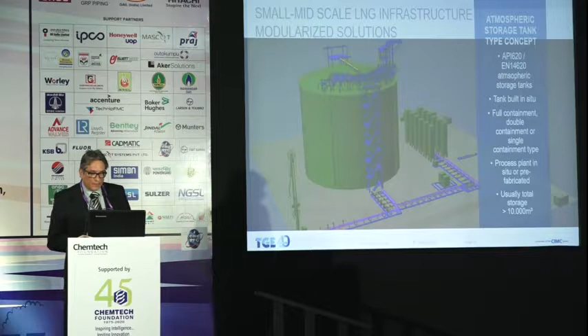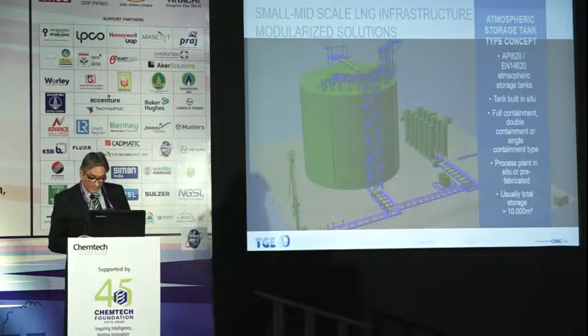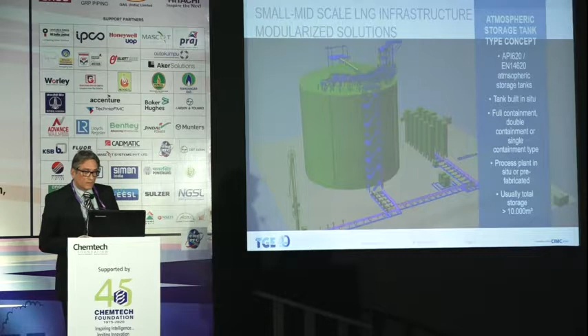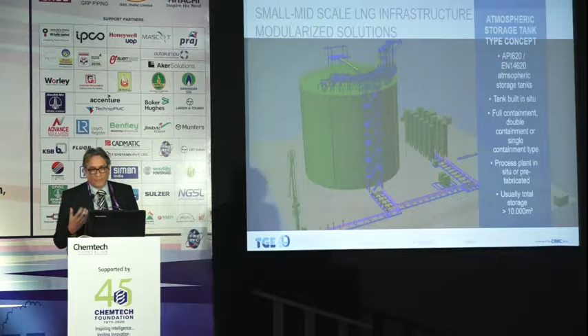authorities like to see a full containment solution, which is absolutely state of the art. Also here, as you can see, this is a very standardized and modularized design approach. This type of storage is usually applied for storage capacities above 10,000 cubic meters due to economy of scale. For smaller terminals, this would be more expensive than the pressurized solutions.